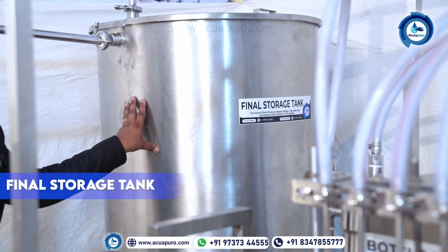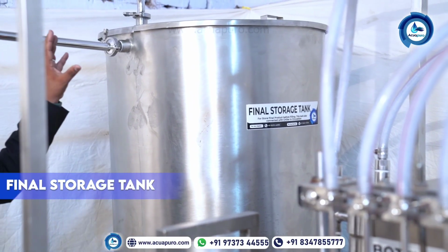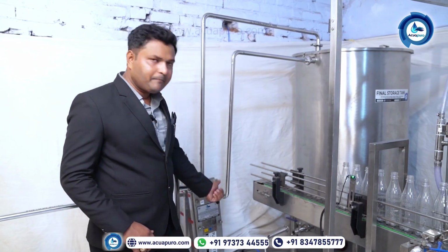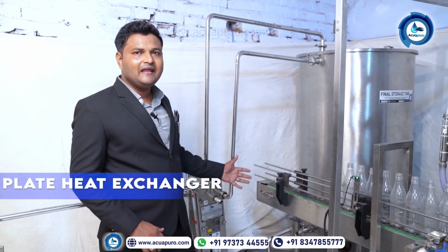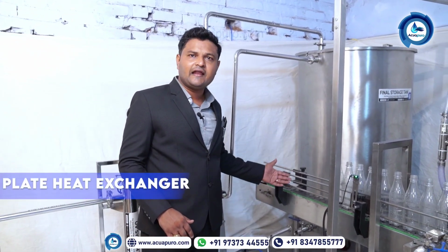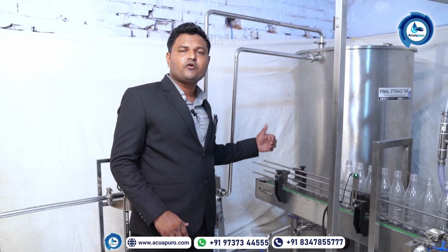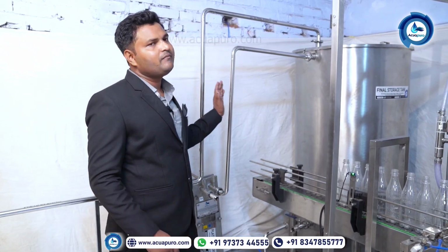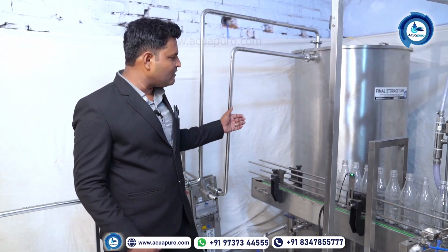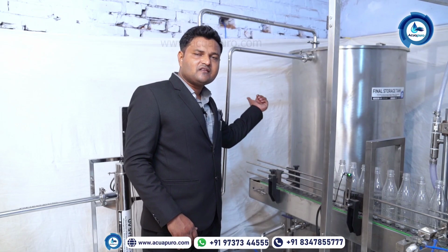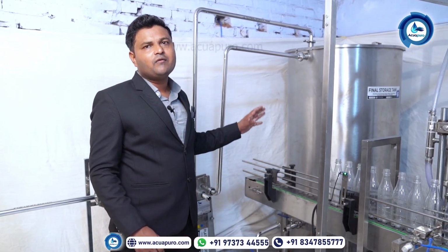This is the final storage tank where your final product comes in. Again this is a plate heat exchanger where the heat will transfer from one end to another end. Here we are using an industrial chiller to decrease the temperature of your end product. Inlet material will be nearby 35 to 40 degrees when you start this machine, and when you start the chiller, which we are putting outside of the premises, the temperature will become less than 10 degrees. If you want to decrease the temperature more, instead of water you can use glycol as well.